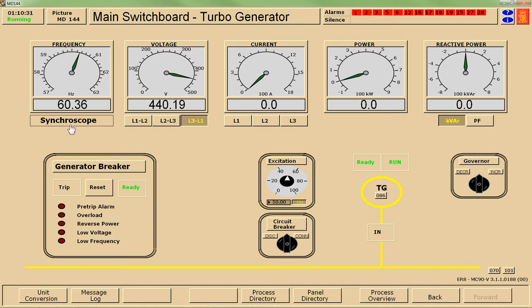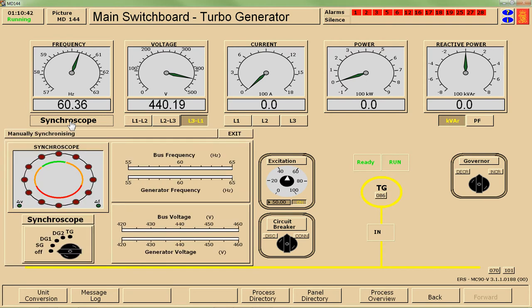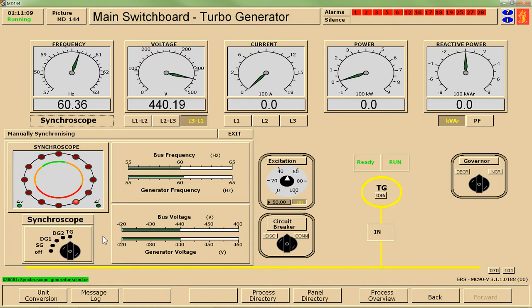In order to synchronize I need to read data for this generator compared to the grid or the bus, so I'm going to need to use my synchroscope. The synchroscope has its own page but I can also bring up a small window by clicking on synchroscope. I've pulled up my synchroscope window and we can see a little indicator, a switch, and some graphs. Nothing seems to be running — in order for it to run I need to move my switch over to the turbo generator position, and now things seem to be working. My synchroscope has this red dot moving around.